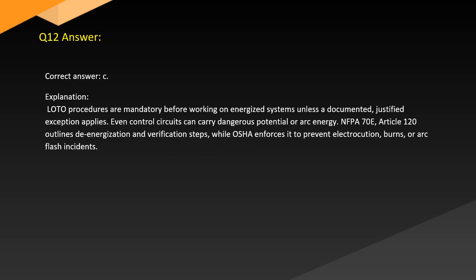Answer. Correct answer: C. Explanation. LOTO procedures are mandatory before working on energized systems unless a documented, justified exception applies. Even control circuits can carry dangerous potential. NFPA 70E Article 120 outlines de-energization and verification steps, while OSHA enforces it to prevent electrocution, burns, or arc flash incidents.